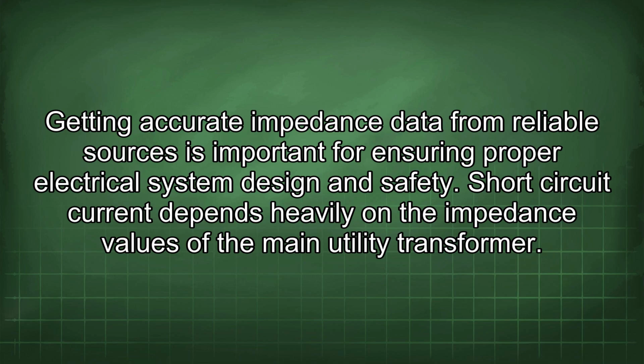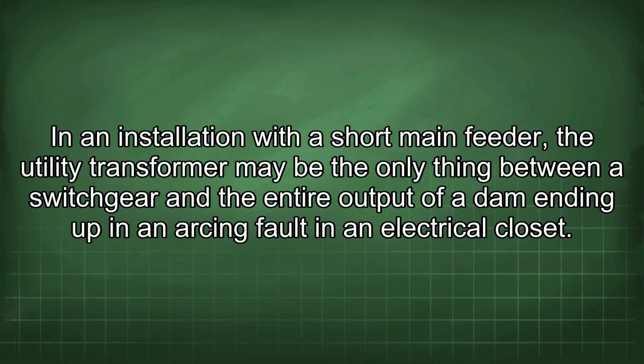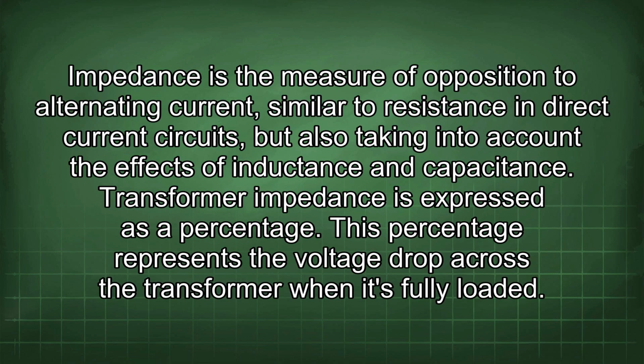Short-circuit current depends heavily on the impedance values of the main utility transformer. In an installation with a short main feeder, the utility transformer may be the only thing between a switchgear and the entire output of a dam, ending up in an arcing fault in an electrical closet. Impedance is a measure of opposition to alternating current, similar to resistance in direct current circuits, but also taking into account the effects of inductance and capacitance.